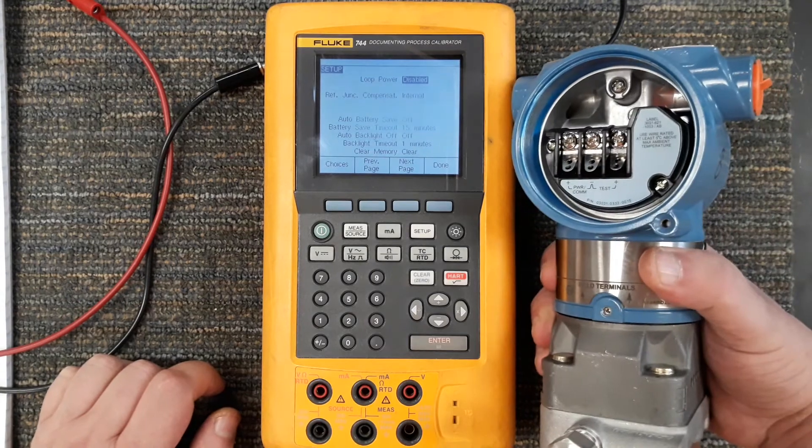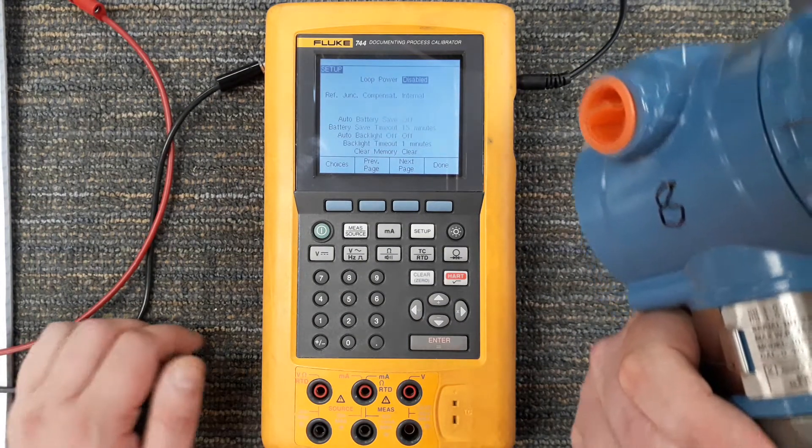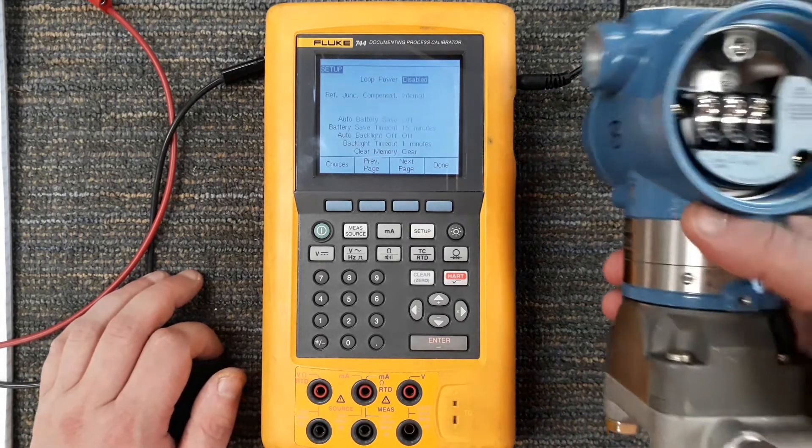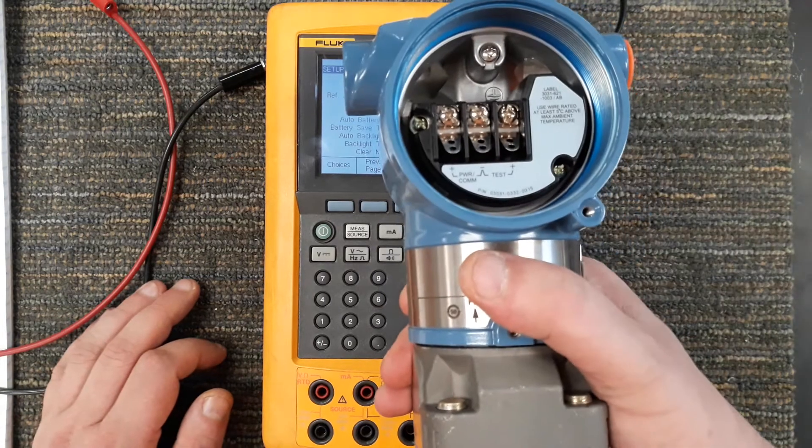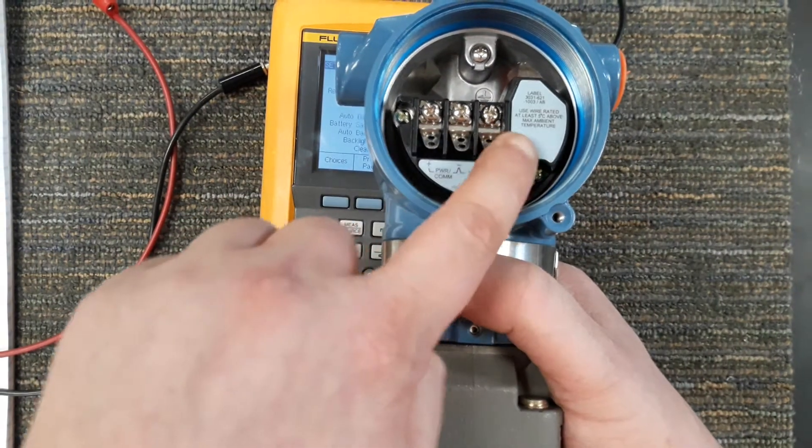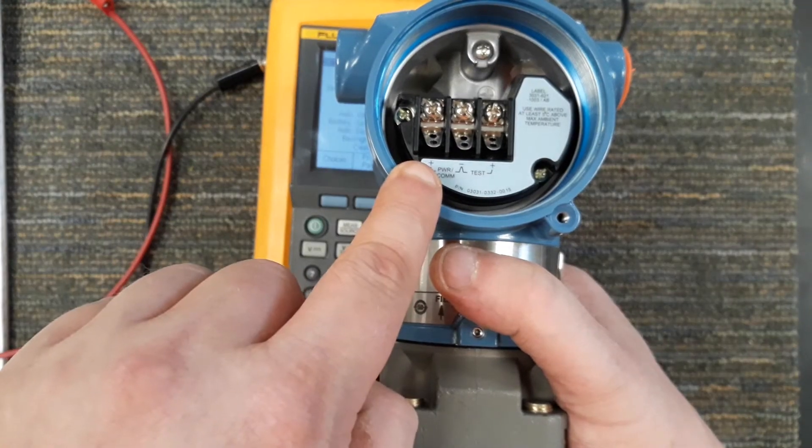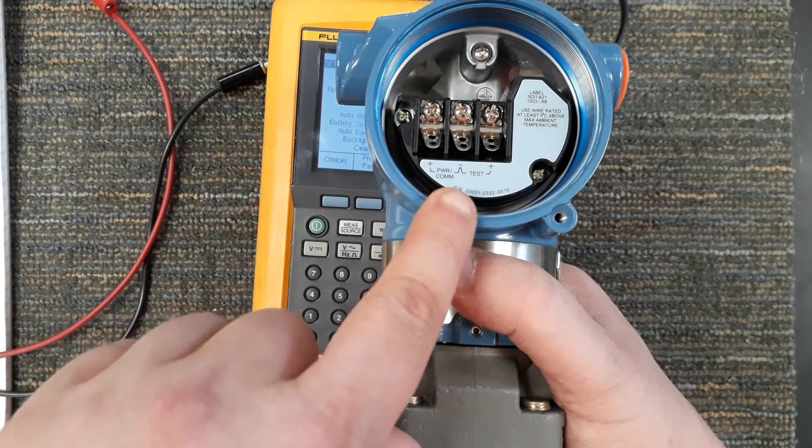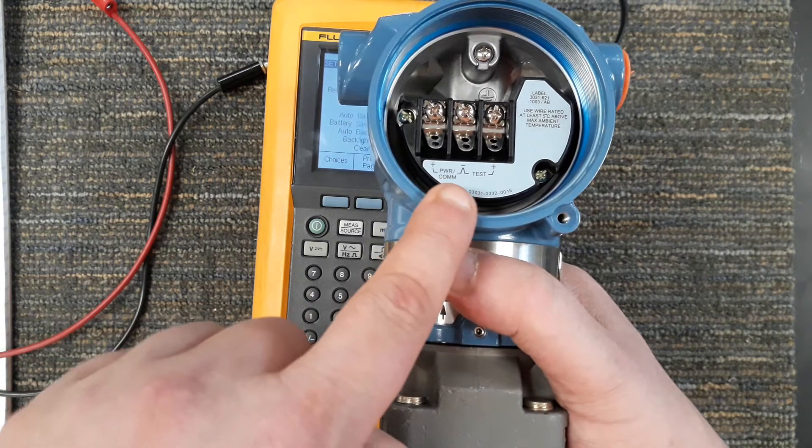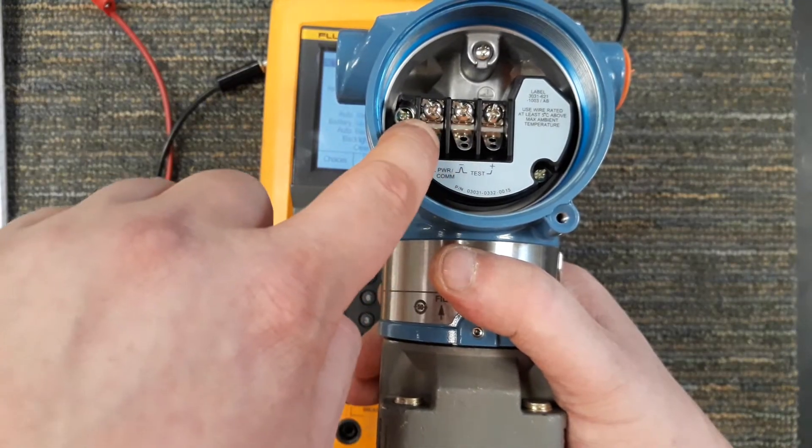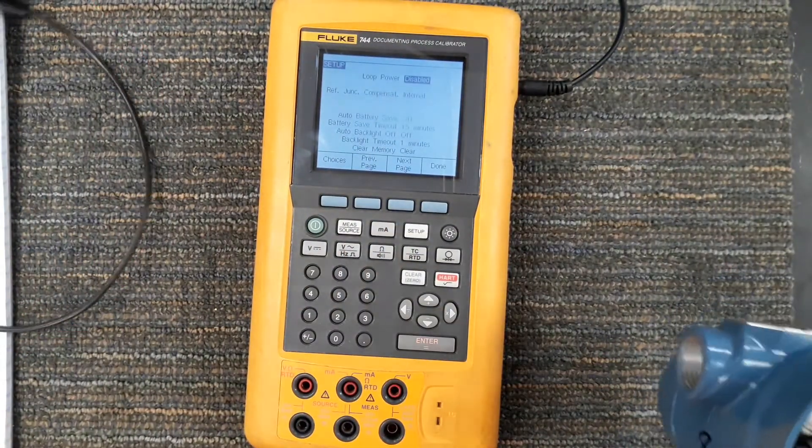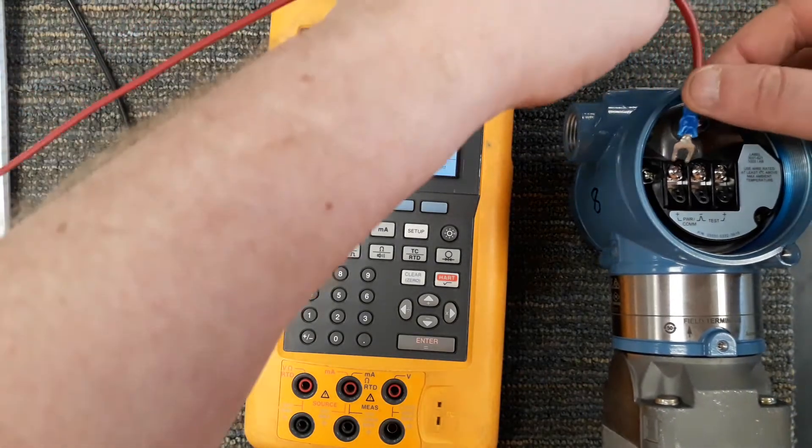This is a differential pressure Rosemount transmitter. If we take a look at it, you can see we have three terminals. One is my positive, one is my negative, another one's a positive. These two where it says power/comm, that stands for power and communication. This is my positive for hooking up power, this is my negative for hooking up power. I'll go ahead and take my red wire which we have terminated with forks.